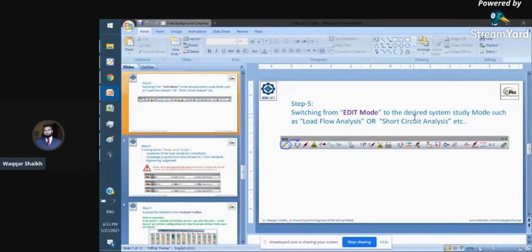This is to see the base conditions in the network, whether it will run successfully under normal operations. Then we can jump into other types of studies like short circuit or arc flash, but the first base level study is always a load flow study. So in this example, we are going from edit mode into load flow mode.